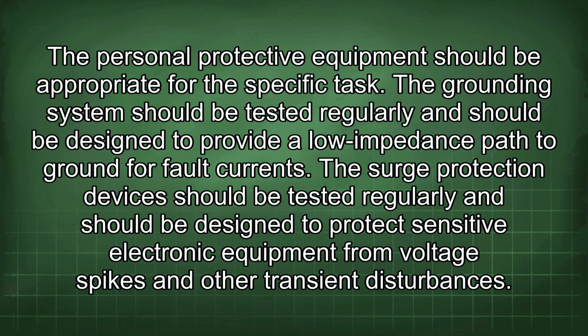The grounding system should be tested regularly and should be designed to provide a low impedance path to ground for fault currents. The surge protection devices should be tested regularly and should be designed to protect sensitive electronic equipment from voltage spikes and other transient disturbances.